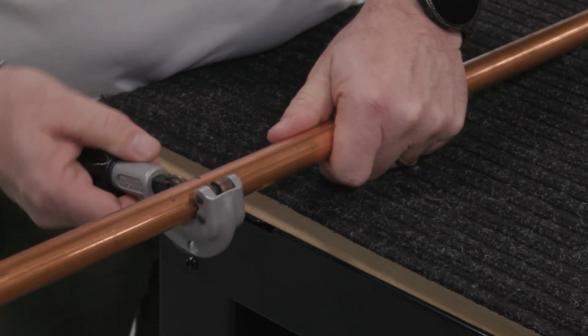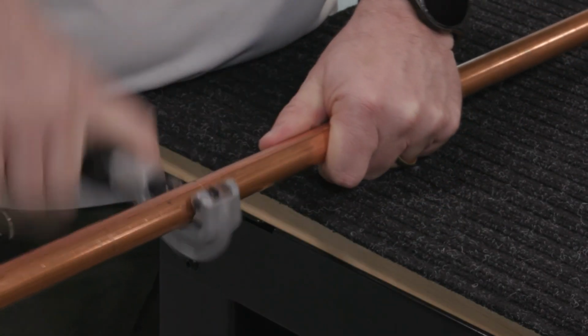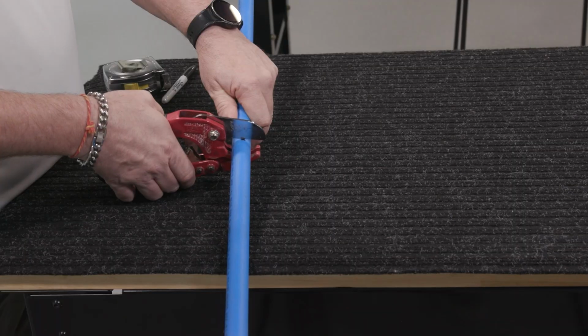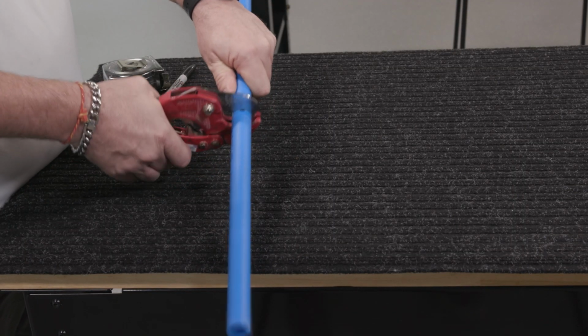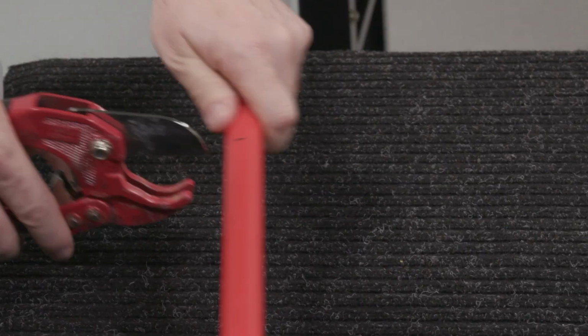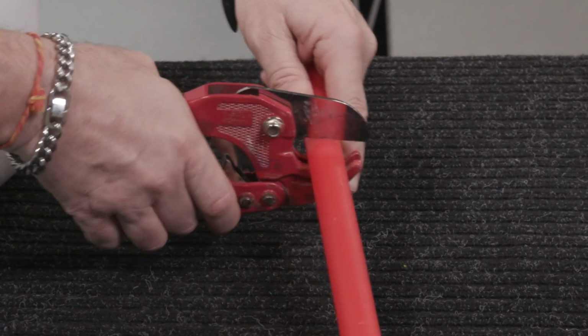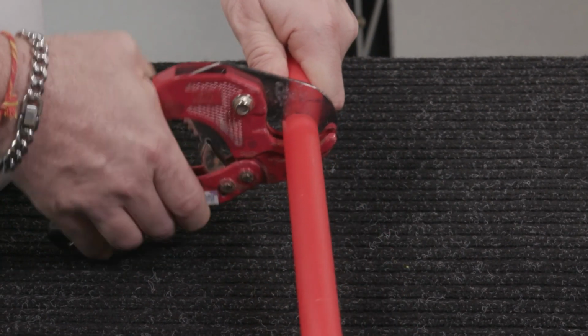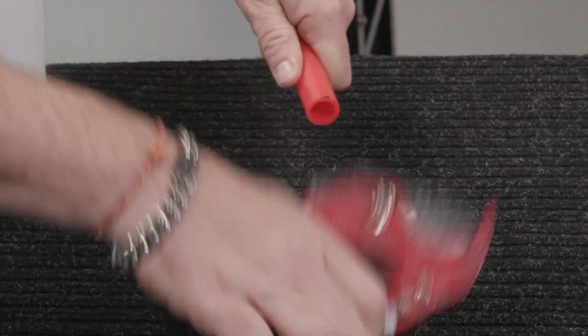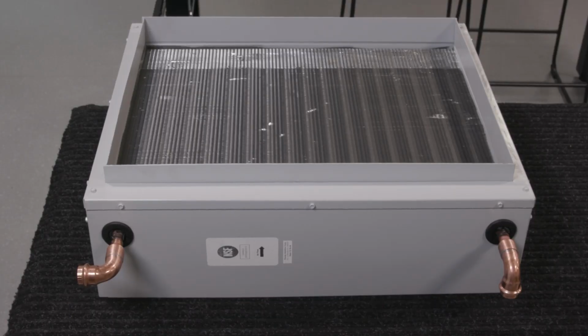For this installation of Kit 1, we are using 3/4 inch copper tubing. However, you can also use 1-inch PEX as well. For Kits 2 and 3, confirm that your plumbing fixtures are compatible with the corresponding temperature and pressure. An appropriately sized hydronic coil.